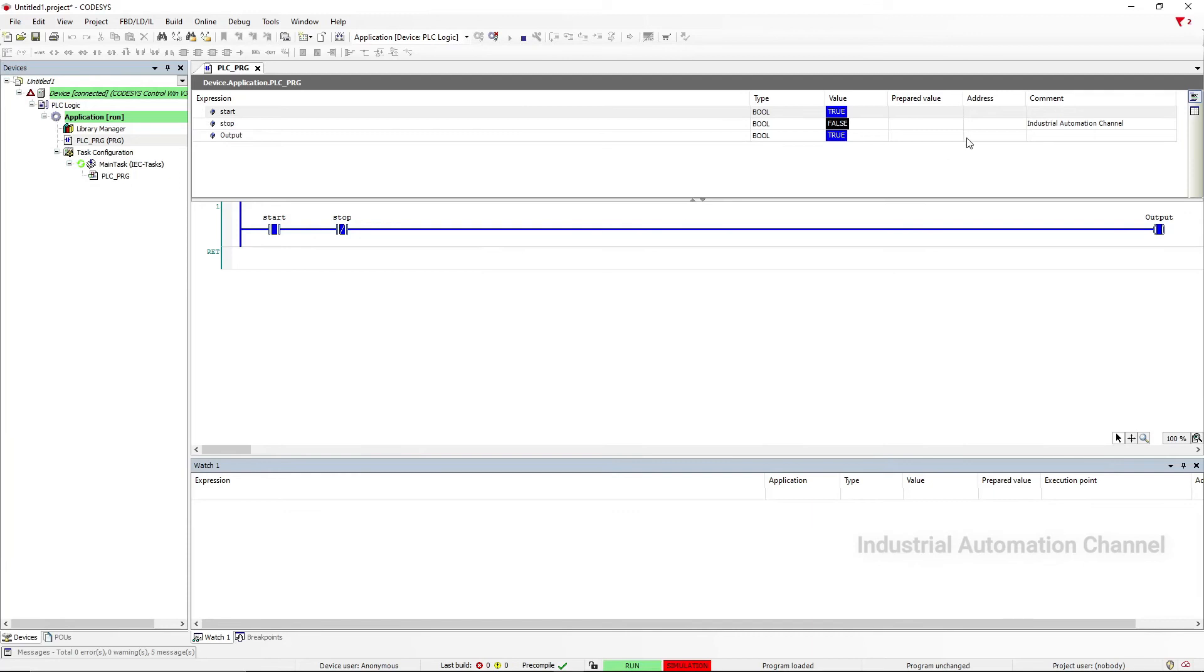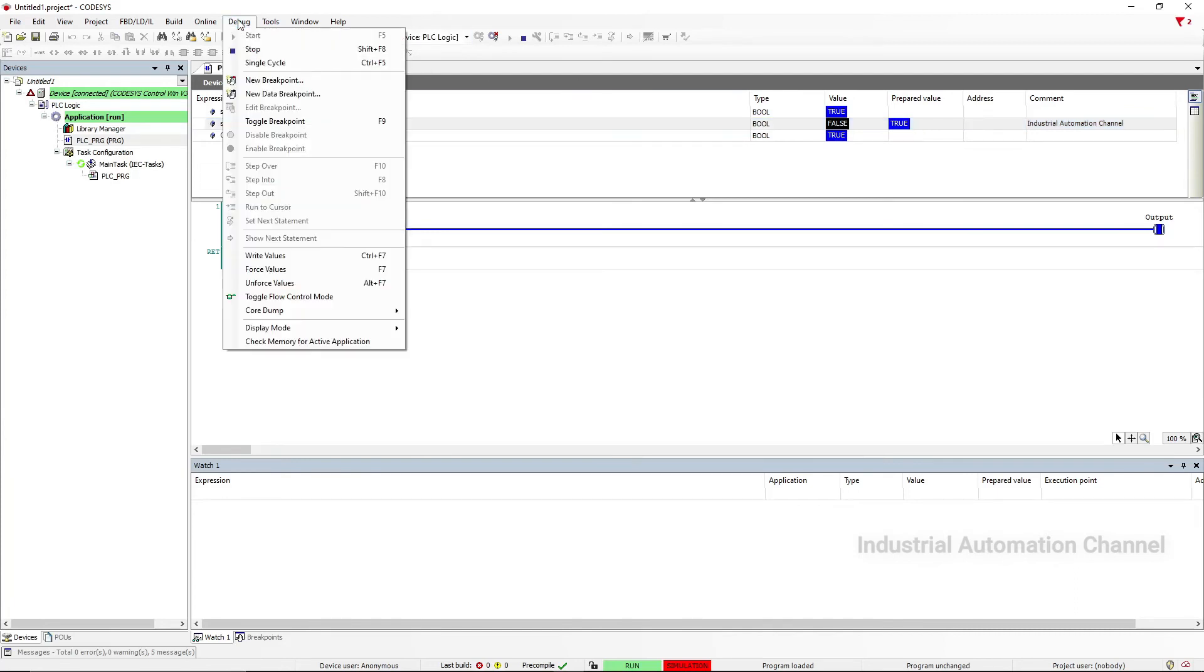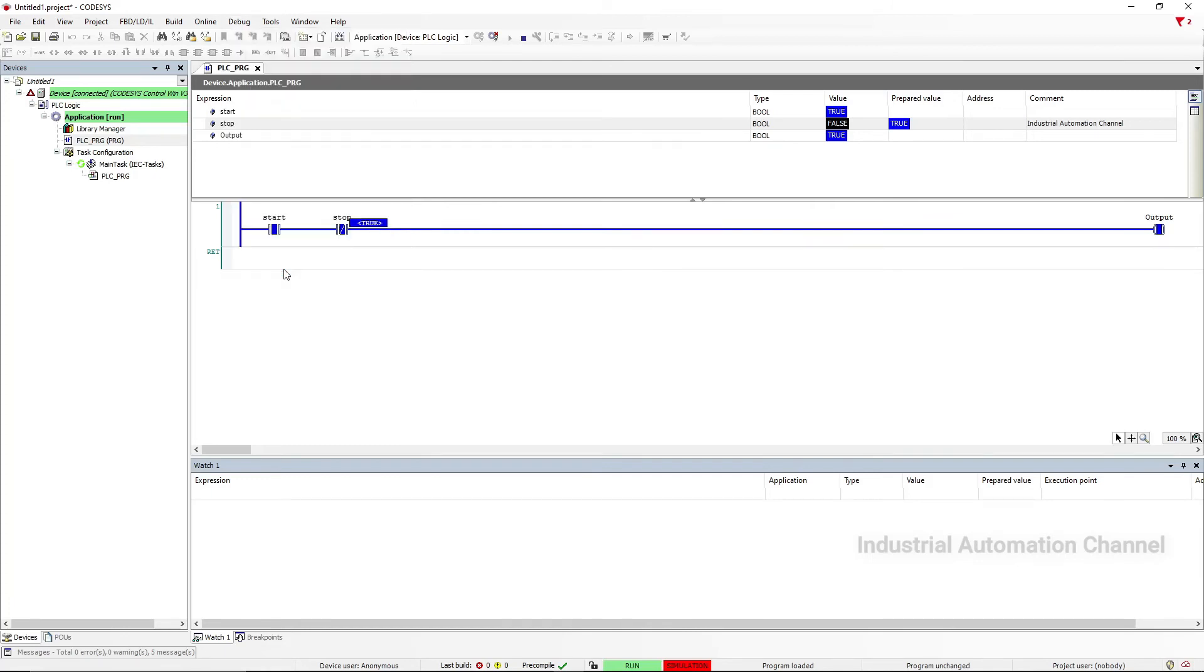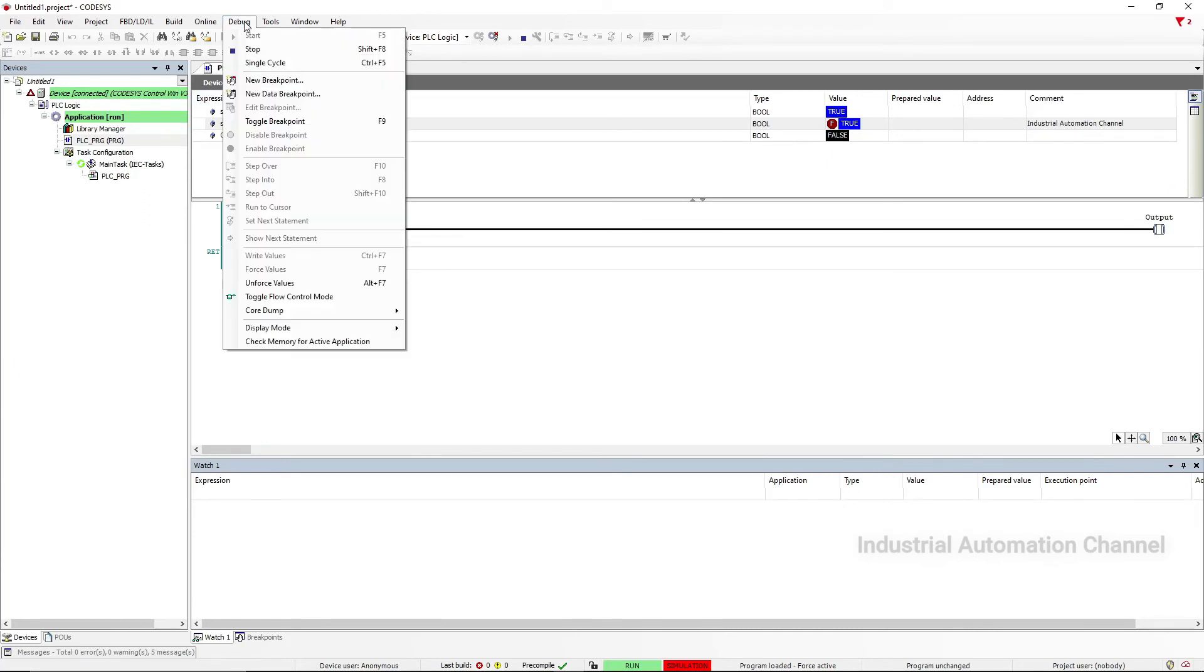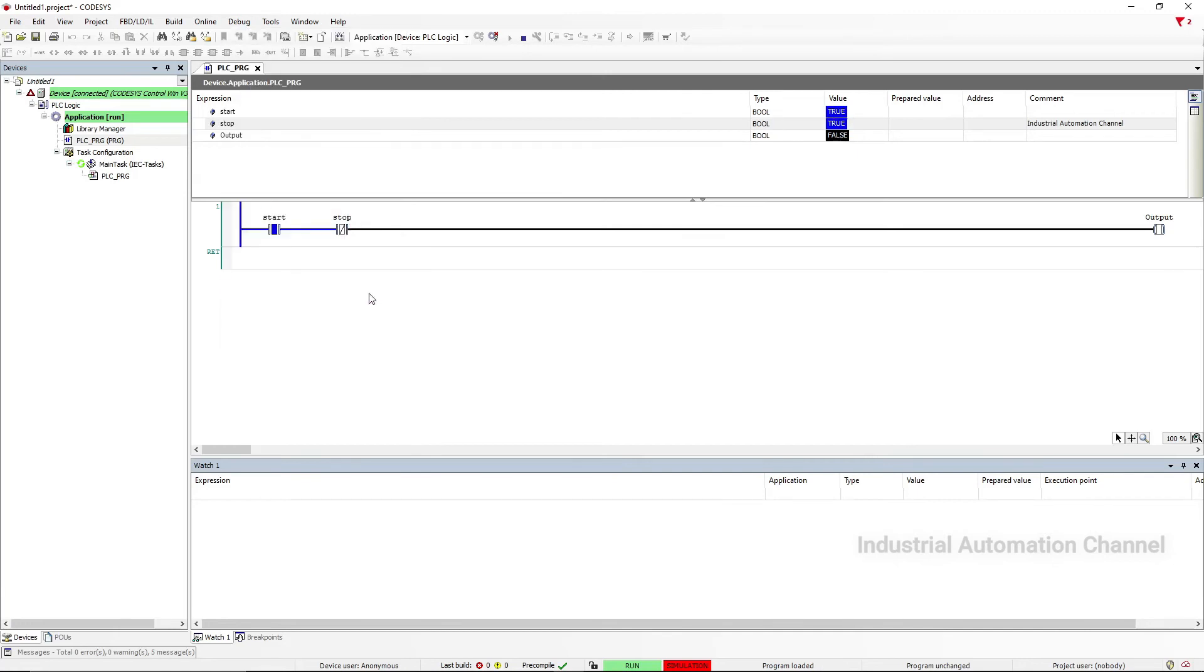You can also force your variables. To do that, select your variable, and after selecting your value, select from Debug Force Value or press F7. There is a little F near the value. It means we have forced our value. With Alt + F7 you can unforce the value. Now the value has changed and there isn't any force sign near the value.